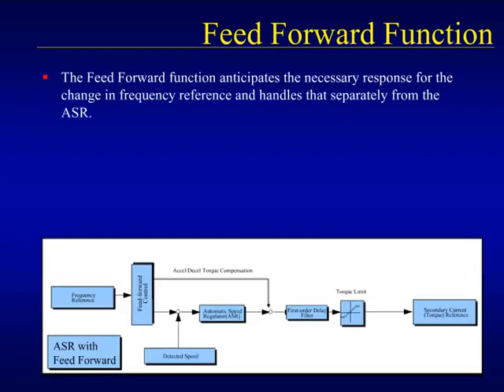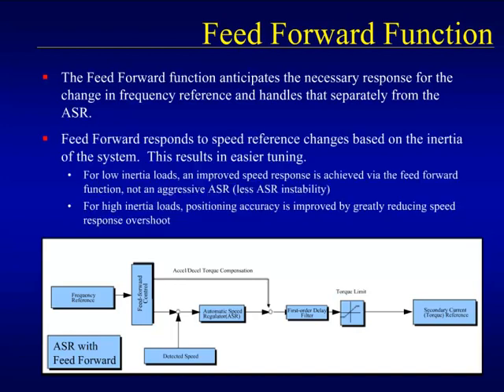The feed forward function will isolate the ASR's reaction to motor speed errors caused by a frequency reference change from the reactions to motor speed errors caused by load changes. By separating the two sources of motor speed errors, the feed forward can more effectively compensate for the errors without the use of overly aggressive ASR gains. How the feed forward function calculates the amount of compensation is based on motor inertia and the inertia of the load. Feed forward will improve the speed profile of a low inertia system without the instability of an aggressive ASR, and will also make positioning of higher inertia systems more accurate by eliminating speed response overshoot.